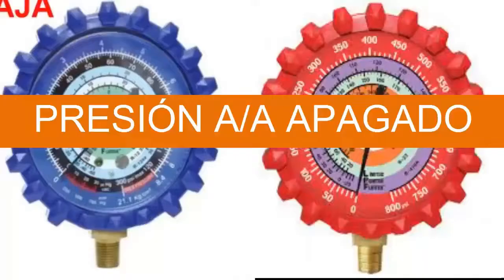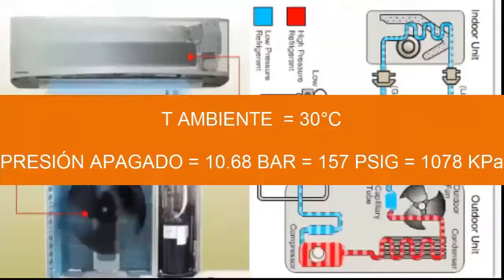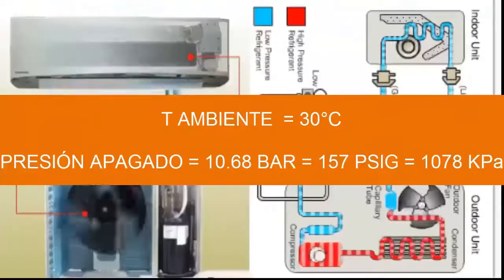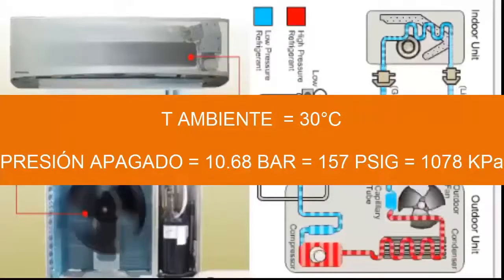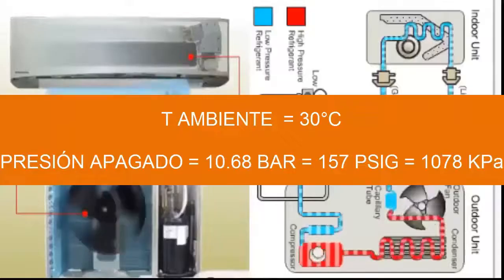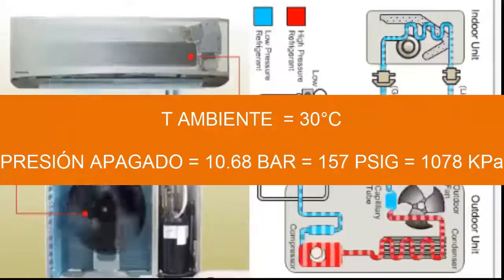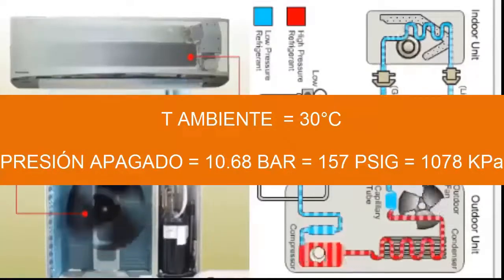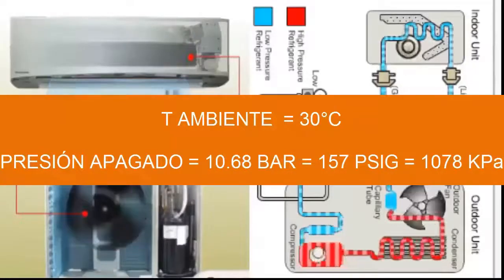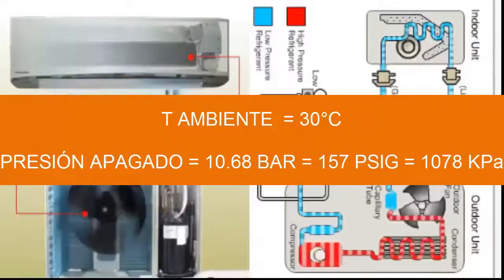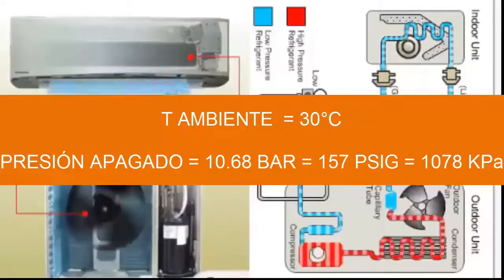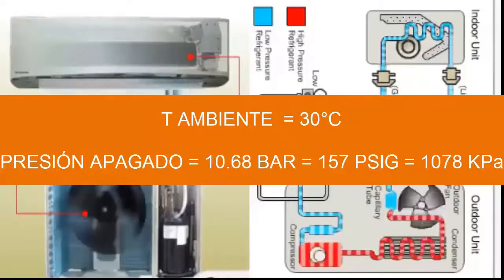For an outdoor environment temperature of 30 degrees Celsius, about 86 degrees Fahrenheit, with the equipment turned off, the gauge pressure — both high and low — according to the table is 10.68 bars, equivalent to 157 psi or 1078.68 kilopascals.